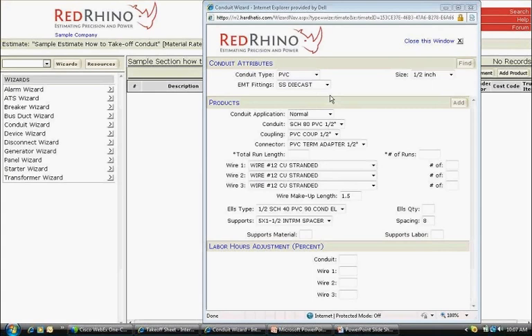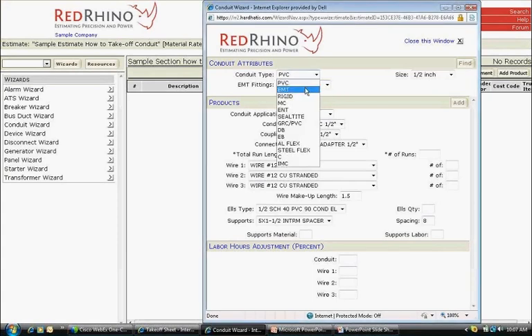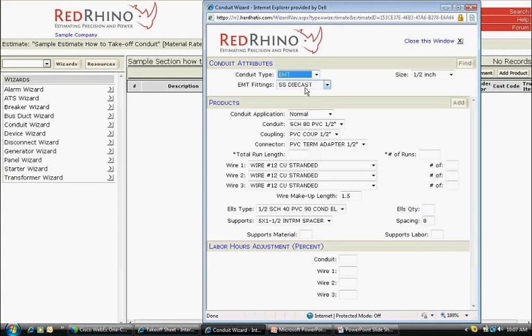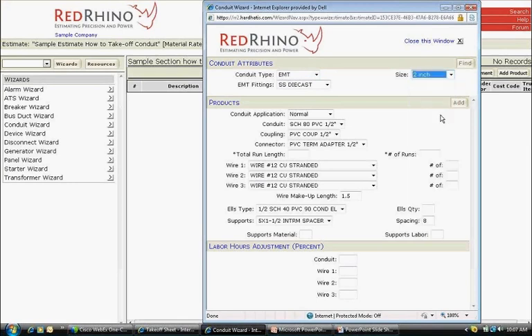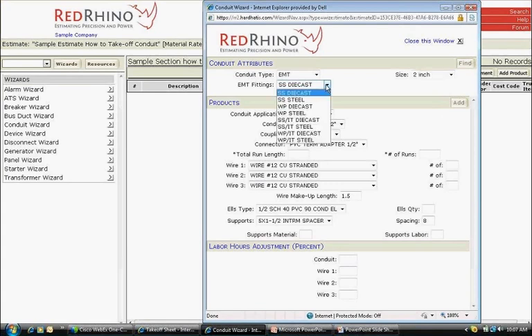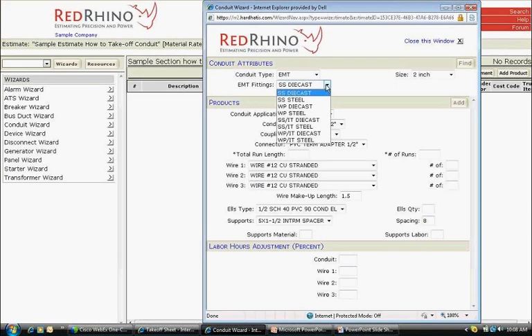On the top of the pop-up next to the words Conduit Type, there's a drop-down that says PVC. I click on that drop-down and select EMT. Next I click the Size drop-down and select 2-inch. Again, the conduit run from the material takeoff is 2-inch EMT with four 3-0 wires. Below the Size drop-down it says EMT Fittings. I click the drop-down and the setting allows to set up whatever type of EMT fittings or input. Many types of fittings are available to select from on the drop-down. There's four different types. There's steel or die cast. SS means set screw. WP means weatherproof or compression fittings. SSIT means set screw insulated throat. WPIT means weatherproof or compression fittings insulated throat. For this example, we'll use SS die cast. So I'll click on that.